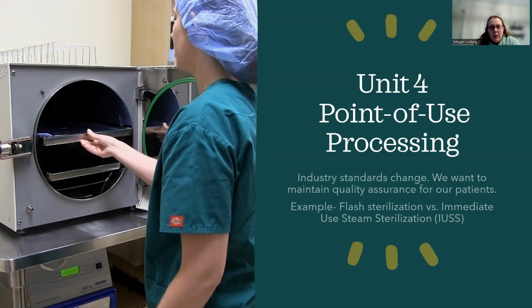But I have seen surgeons who are very demanding or antsy, or they want to get on with their day and they need it right then. Everything's right then, right? So they would put it in a flash sterilizer for the next case instead of going through the proper process. They basically traced through time that you're more likely to have SSIs in those cases if you're not properly decontaminating an item for the next case. You're definitely going to increase the patient's risk for infection, and we don't want to do that.